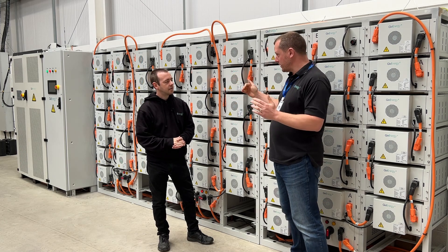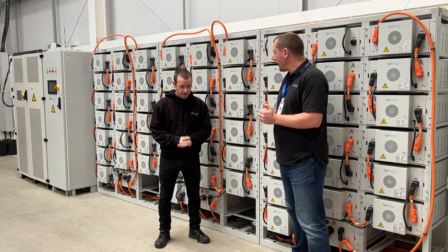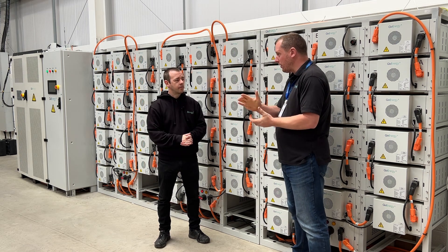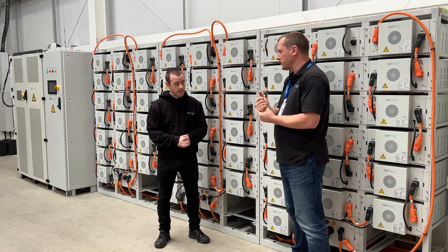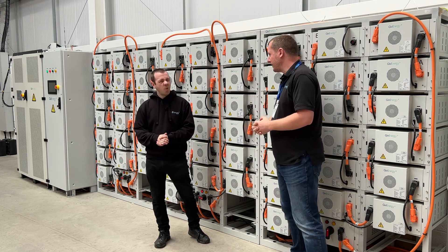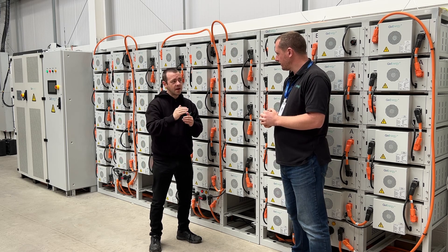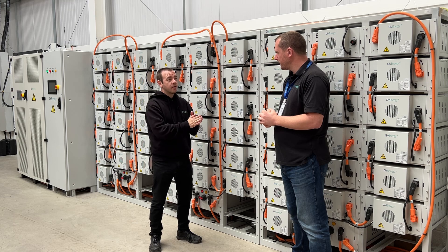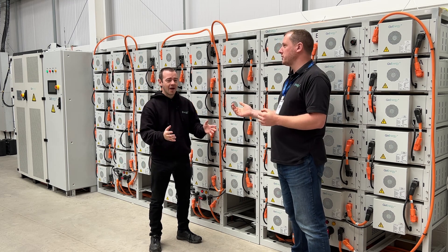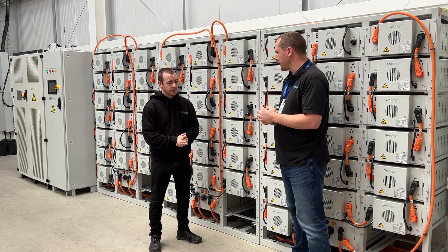That will go with anything between a 30 and a 500 kilowatt inverter. If you want more, you then have multiples of that. The largest one we have out in the field at the minute is 4,800 kilowatt hours — that is 4.8 megawatt hours. To put that into context, I have a fairly decent home battery that's 19 kilowatt hours, and 4,800 kilowatt hours is about 600 days of average home usage.